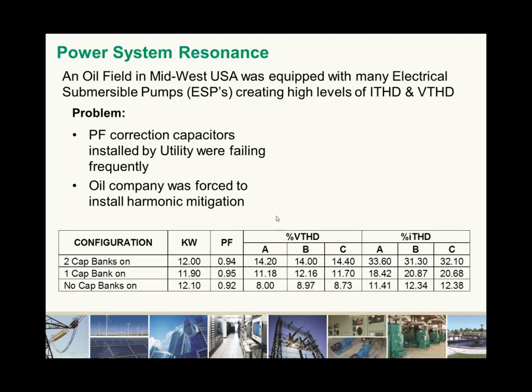So when we were asked to investigate the site, we saw that the voltage distortions were extremely high, figured that was due to a resonance condition, and asked the utility to start switching off the cap banks and see what effect it would have. They had two switchable cap banks. When they turned one of the cap banks off, the voltage distortion dropped to the 11 to 12% range. Current distortion dropped to the 18 to 20% range.